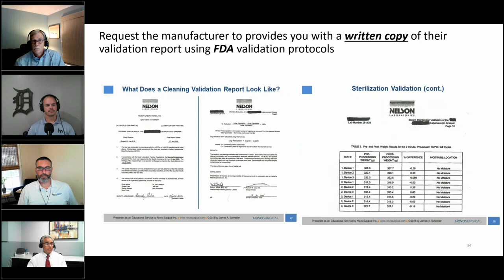In this, you see that they selected 3 instruments and soiled them, and after that, they all showed negative. These are the documents that the manufacturer must submit with their 510(k) clearance or PMA approval. So if they have submitted them to FDA, ask for those written IFUs to see how they validated them. Moreover, if you have an issue, you should be able to validate them yourself, or if you have a problem and a lawsuit comes up, send them to a third party and be able to validate those.